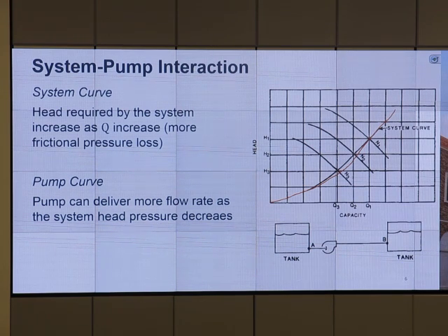So basically, you get the Reynolds number. From the Reynolds number, get the friction factor. From the friction factor, use 2f rho V squared over D, then get minus dP/dz, or frictional pressure loss per unit length. You know the length, then you get pressure loss. So that gave you the system curve. It tells you, if we have that much flow rate, that is the pressure drop. Then for the pump side, if we have that much head or that much restriction in the pipe, that is the flow rate that the pump can deliver. Wherever they cross, that is the operating point.